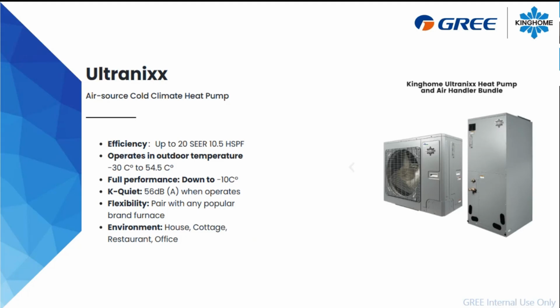Very efficient. You can operate the unit from minus 30 degrees Celsius to 54.5 degrees Celsius. You can get 100% capacity at minus 10 degrees and really quiet units. And it's very flexible regarding the installation on any types of air handler or furnaces. All you need is a case coil with a TX valve. We're going to see through this presentation how we're going to install those big guys out there on the field.